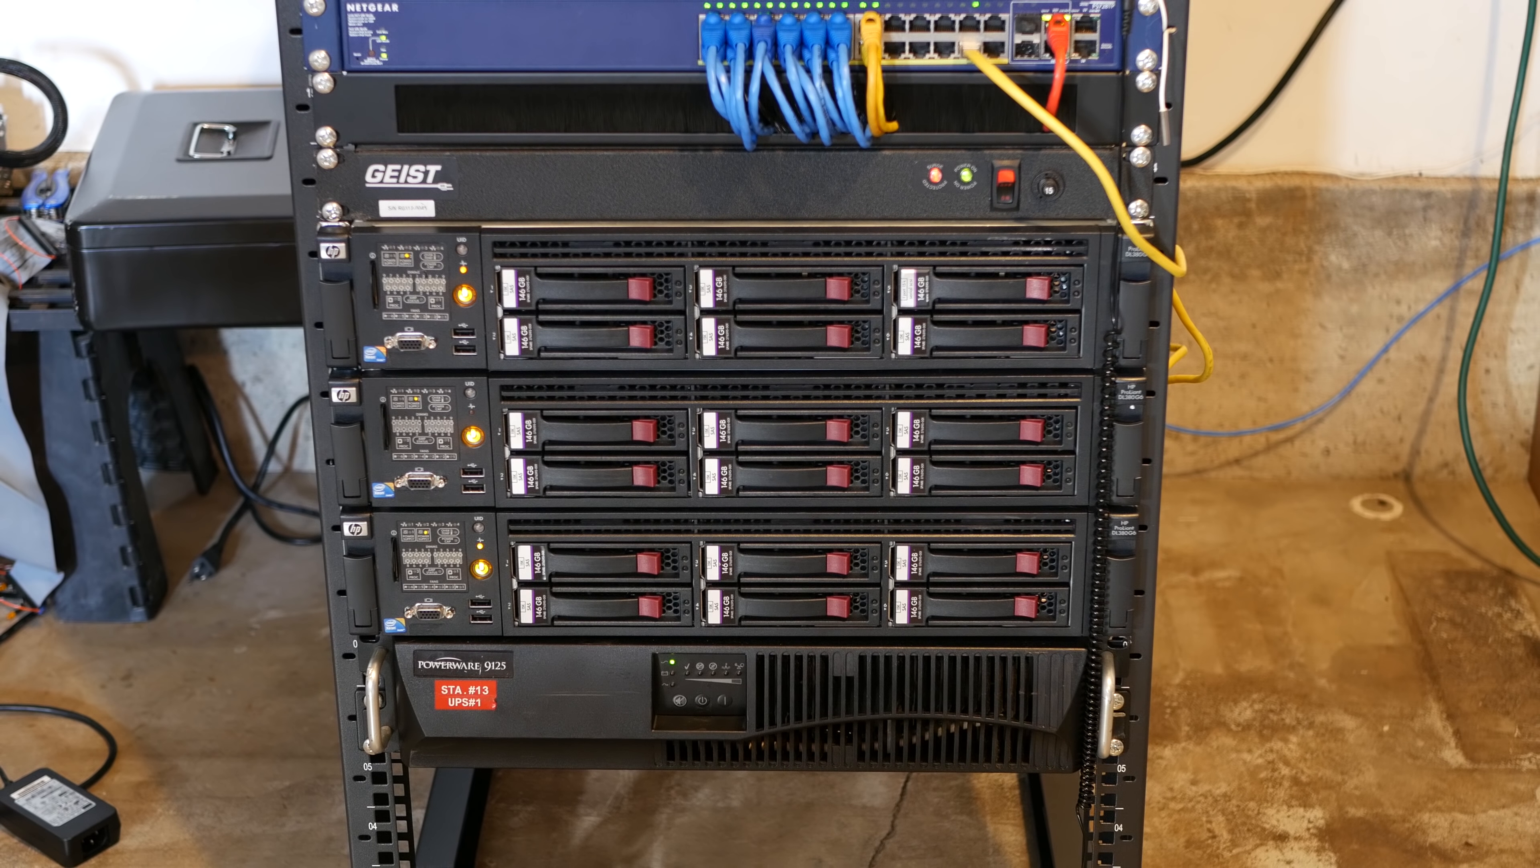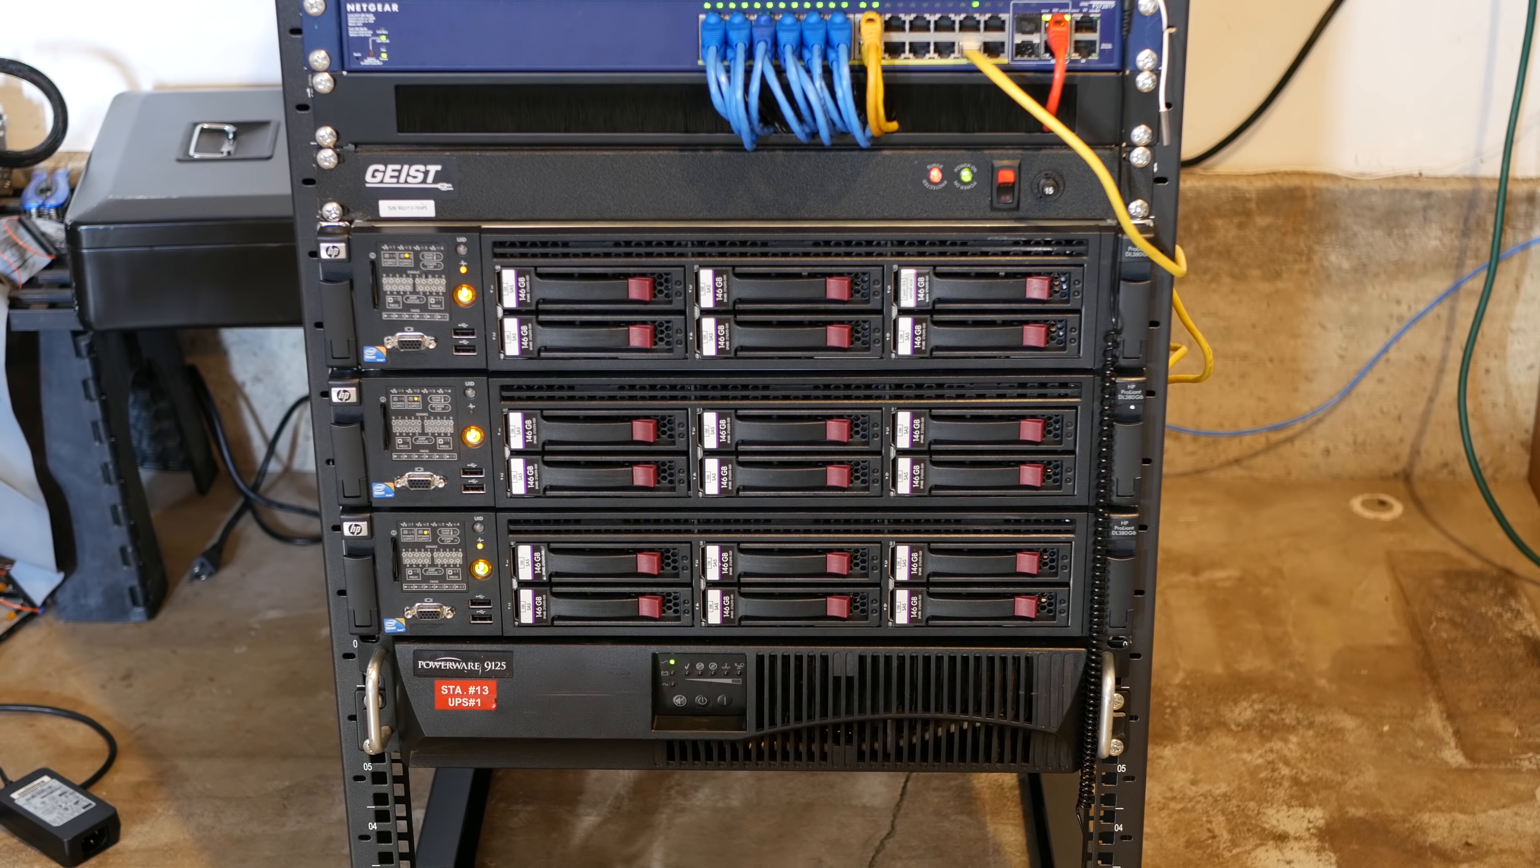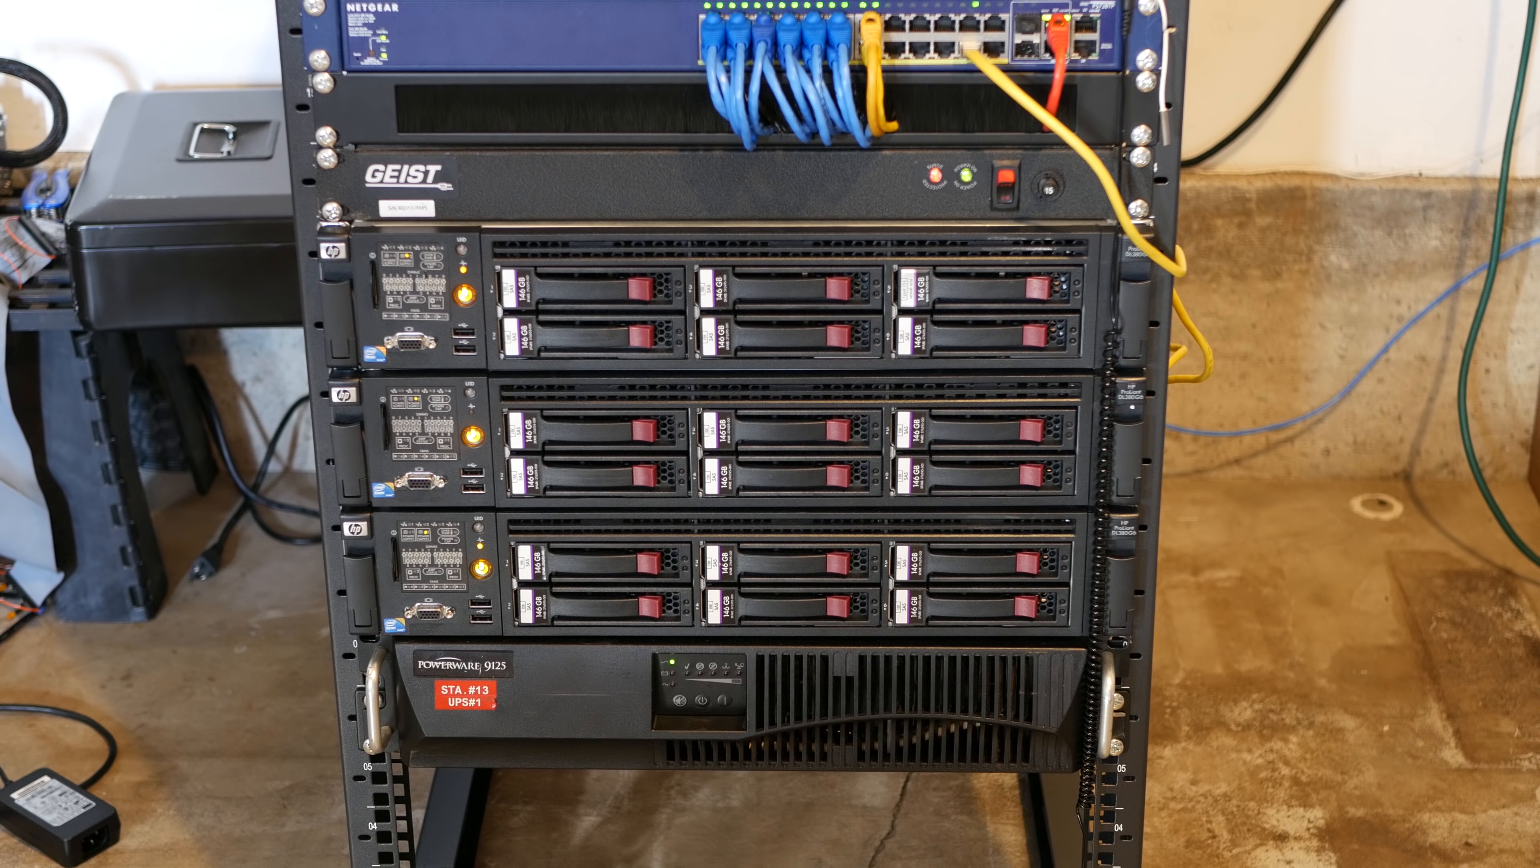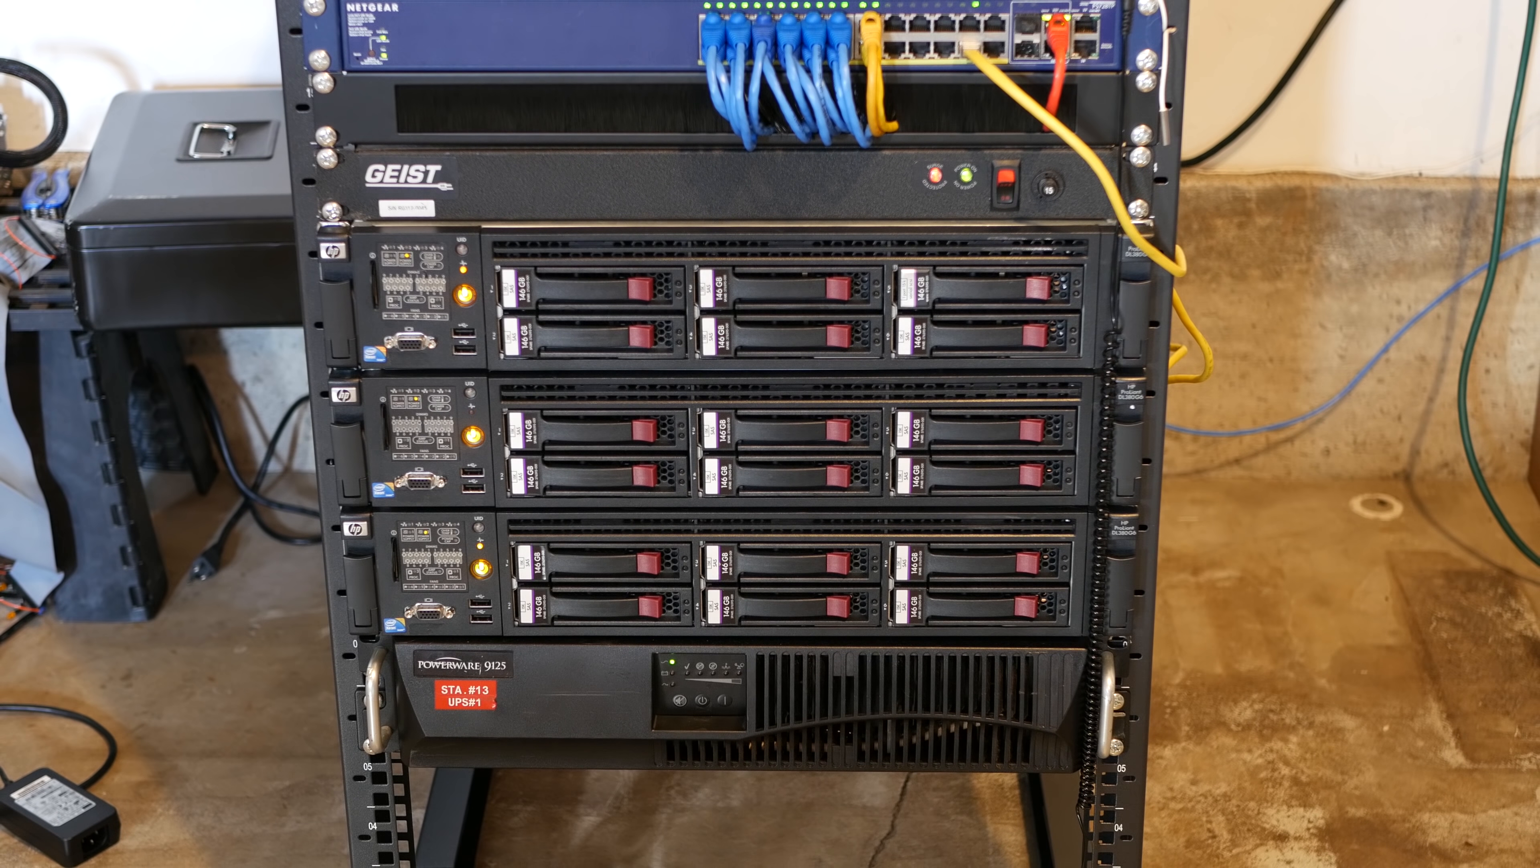The way that it works is basically when it senses that there's no power, it sends a shutdown signal via the network to all the servers if they're on. And then I have set a time for it to wait for the servers to shut down. And then once all the servers have shut down, then the UPS shuts down so that we're not having this running. Because this thing will run for about an hour if nothing's drawing power from it, probably or longer, because that switch will still be drawing power from it. So that's basically everything that's in the server rack. And now I'm gonna give you a tour around the other stuff.